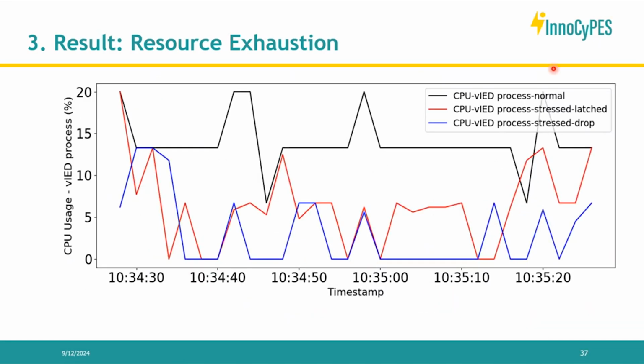Here you see it more clearly, because when the signal is dropped, you can understand why: the CPU usage of the process was almost at 0% half of the time, meaning the process barely had any time to process all the packets being sent. That is why it was never able to detect the fault or send the trip, and that is why we categorized it as trip dropped.